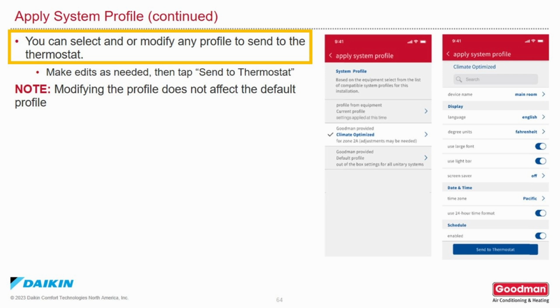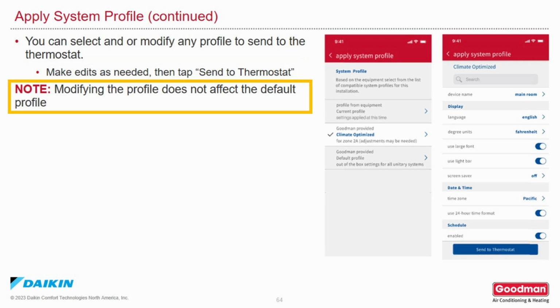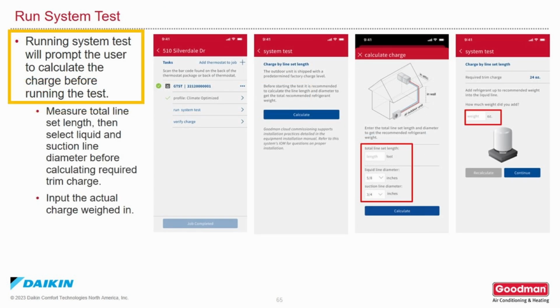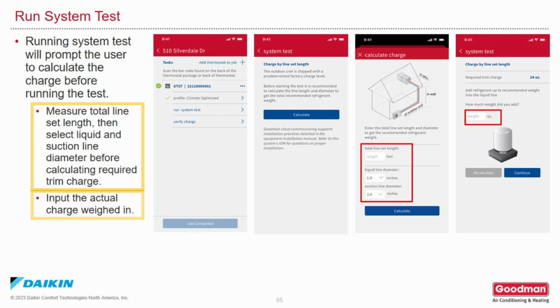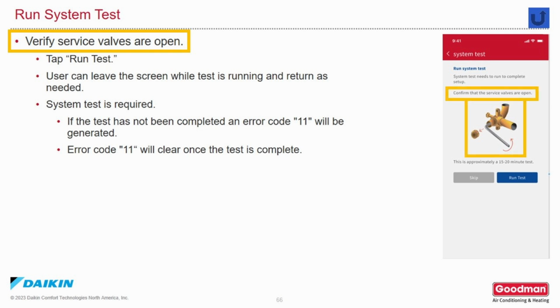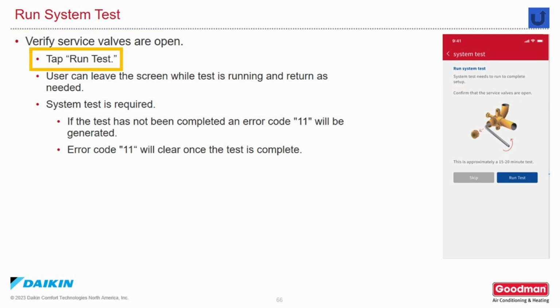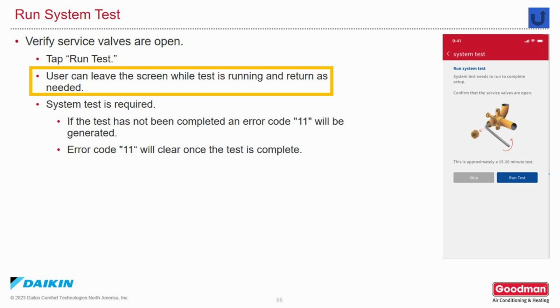You can select and/or modify any profile to send to the thermostat. Make the edits as needed, then tap Send to Thermostat. Modifying the profile does not affect the default profile. When you're running a system test, you will be prompted to calculate the charge before running the test. Measure the total line length, then select liquid and suction line diameter before calculating the required trim charge. Enter the actual charge you weighed in. Verify that the service valves are open. Tap Run Test. Then you can leave the screen while the test is running and return as you need to.